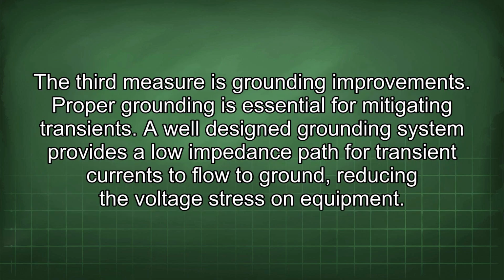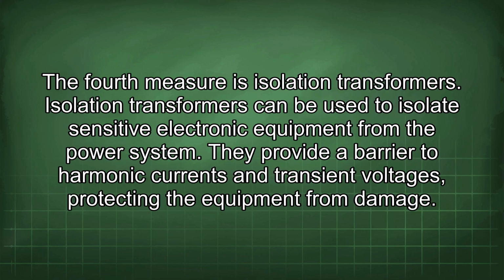The third measure is grounding improvements. Proper grounding is essential for mitigating transients. A well-designed grounding system provides a low-impedance path for transient currents to flow to ground, reducing the voltage stress on equipment. The fourth measure is isolation transformers. Isolation transformers can be used to isolate sensitive electronic equipment from the power system. They provide a barrier to harmonic currents and transient voltages, protecting the equipment from damage.